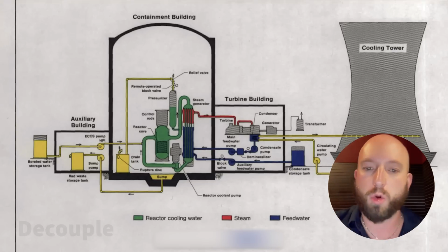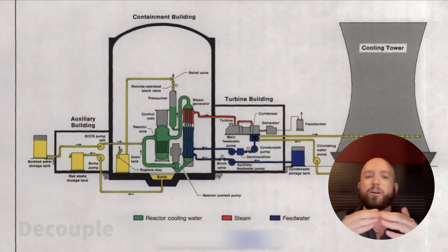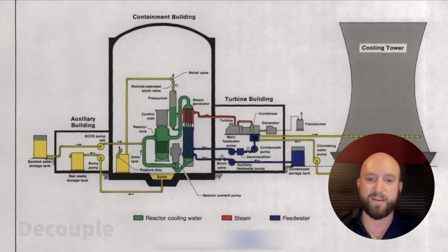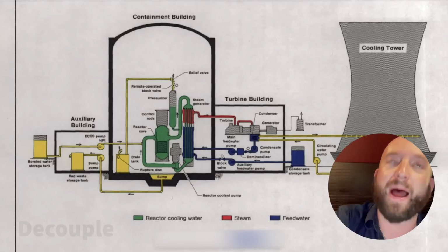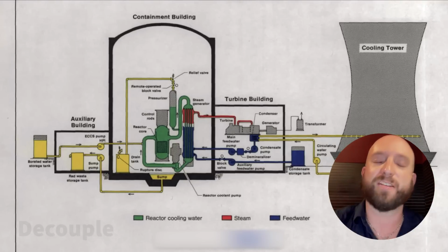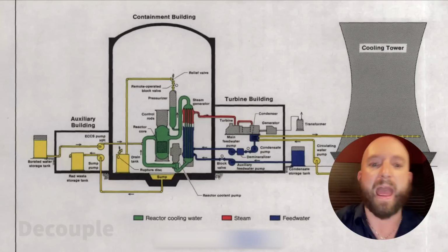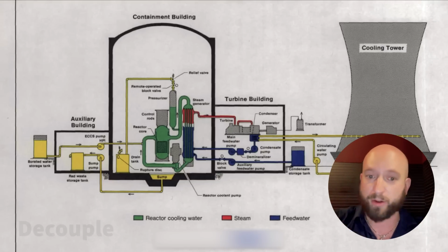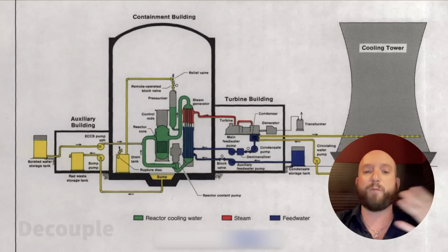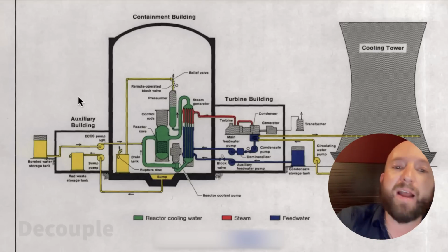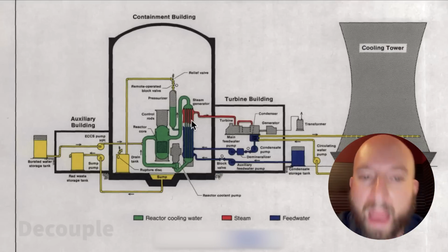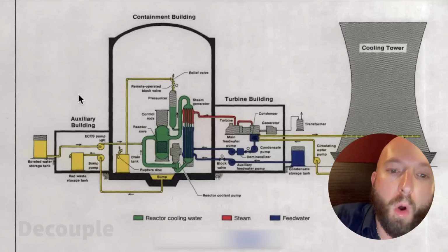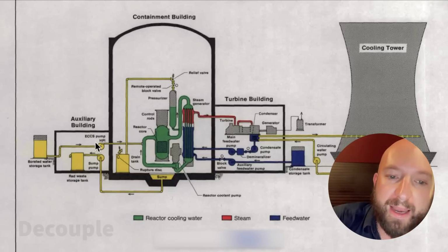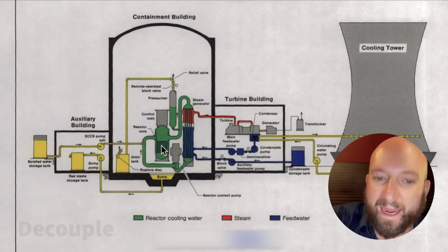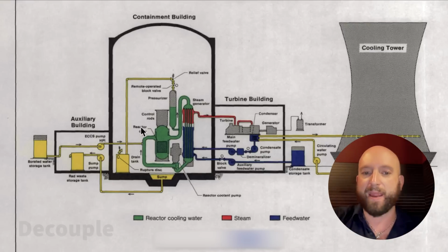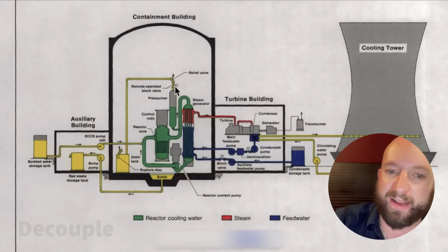And this is where that emergency core cooling system comes into play. The emergency core cooling system, like all the emergency systems in a nuclear power plant, is controlled by a system called the engineered safety feature actuation system. It is also monitoring a bunch of parameters, even as the reactor shuts down, to see if we have a leak or a LOCA situation. And because the pressure in the reactor coolant system is rapidly dropping, the emergency core cooling system automatically turns on and begins injecting water back into the reactor coolant system, more than making up for the amount of water that's leaking out of that stuck valve.